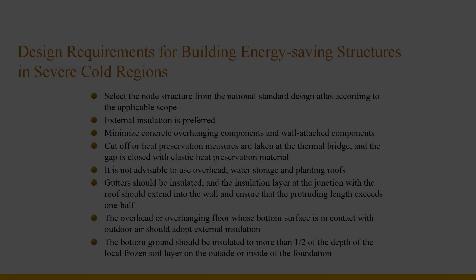Severe cold regions have the following requirements for building energy-saving structure design. 1. Select the node structure from the National Standard Design Atlas according to the applicable scope. 2. External insulation is preferred. 3. Minimize concrete overhanging components and wall-attached components. 4. Cut-off or heat preservation measures are taken at the thermal bridge, and the gap is closed with elastic heat preservation material. 5. It is not advisable to use overhead water storage and planting roofs.